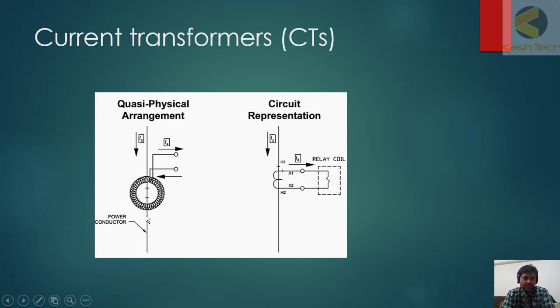This transformer is actually stepping the voltage up and it is stepping down the current. So for example, a CT has a turn ratio 100 by 1. If 100 ampere current is flowing in the primary side, at secondary side you will get 1 ampere.